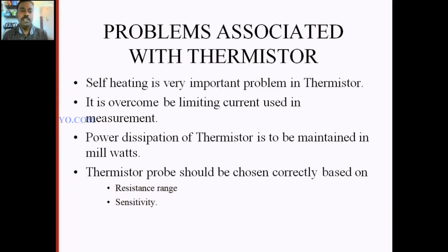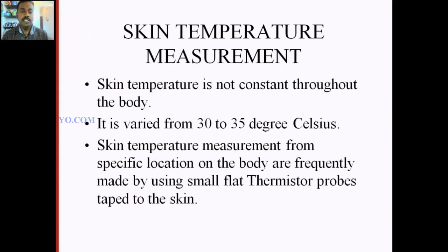The small thermistor probe is connected to the skin. It is just like a sticker placed over the skin, with small wires connected to the temperature measurement instrument. This is a small thermistor wire, a probe with a thermistor, and the end part is the thermistor.